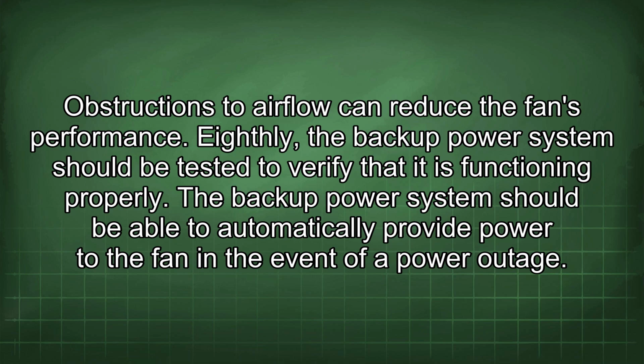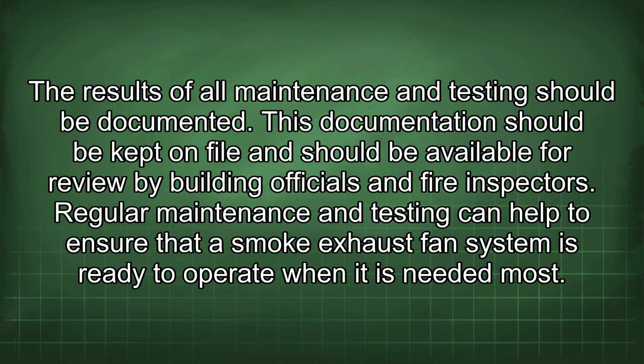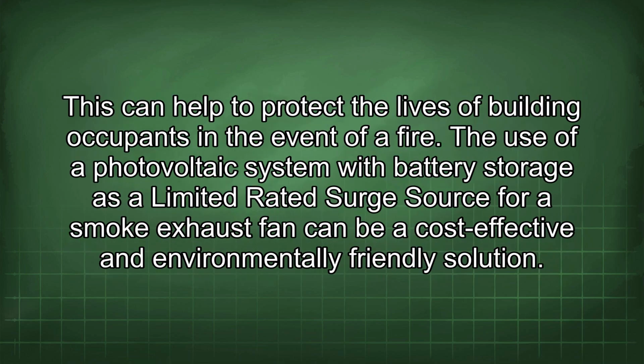Eighthly, the backup power system should be tested to verify that it is functioning properly. The backup power system should be able to automatically provide power to the fan in the event of a power outage. The results of all maintenance and testing should be documented. This documentation should be kept on file and should be available for review by building officials and fire inspectors. Regular maintenance and testing can help to ensure that a smoke exhaust fan system is ready to operate when it is needed most. This can help to protect the lives of building occupants in the event of a fire.